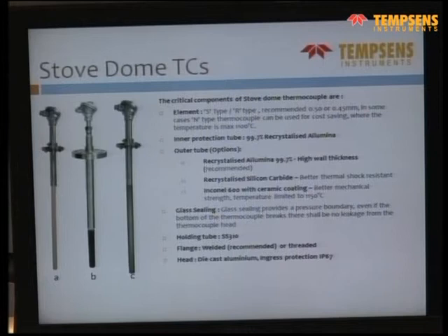As Mr. Clem was telling, silicon can have a lot of drift effect on the platinum thermocouples. So you need a ceramic protection which will insulate it from the metallic part and reduce the possibility of silicon getting into the platinum and drifting the sensor. In all three cases we are using S-type material. N-type is also used in some cases, but inside would be ceramic and outside can be ceramic or silicon carbide, or Inconel in the third case.